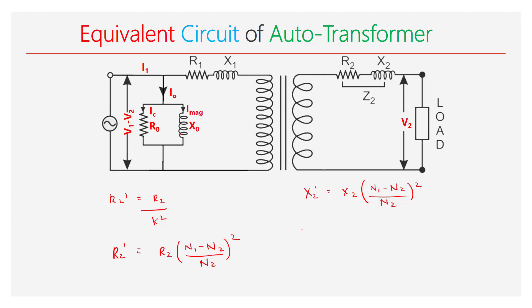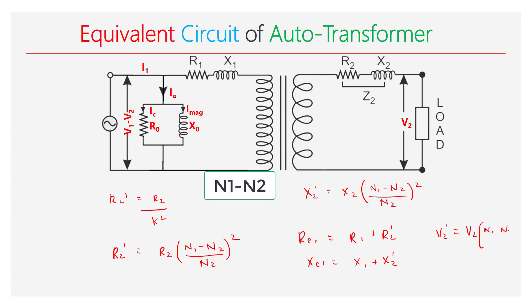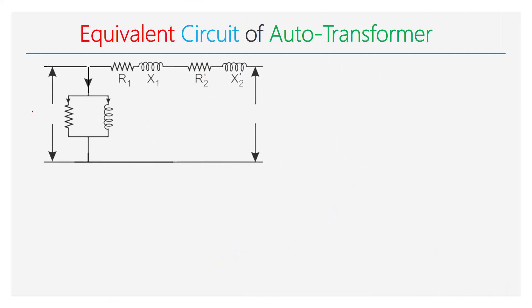After shifting, the equivalent resistance referred to the primary RE1 is given by RE1 equals R1 plus R2'. Similarly, XE1 equals X1 plus X2'. When V2 is shifted to the primary side, V2' is given by V2 multiplied by the number of turns on the primary side divided by the number of turns on the secondary side. The voltage applied across the winding is V1 minus V2, and V2 is written as V2'.